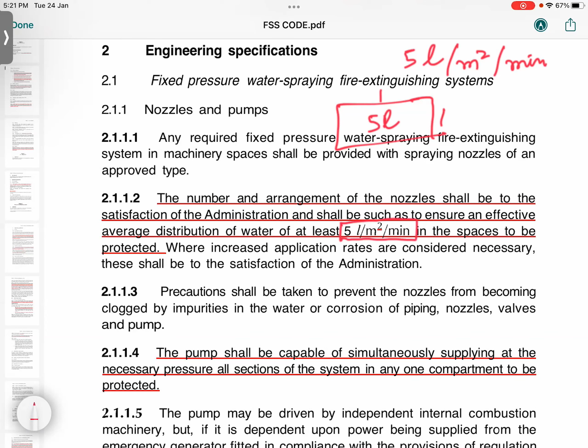This is the fixed pressure water spraying and water mist system. It is all regarding water spraying, water mist, which we call hypermist. First of all, the regulation specifies what you need to cover. The number and arrangement of the nozzles shall be to the satisfaction of the administration, meaning whatever the flag says, and shall ensure an effective average distribution of water of at least 5 liter per meter square per minute.